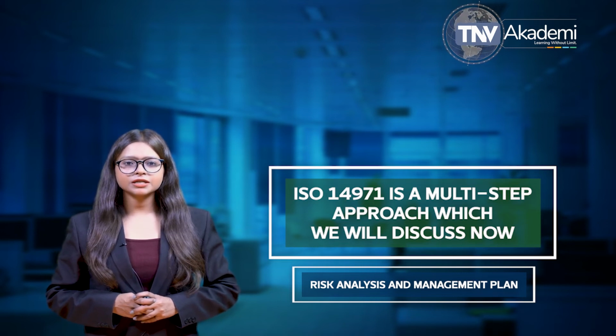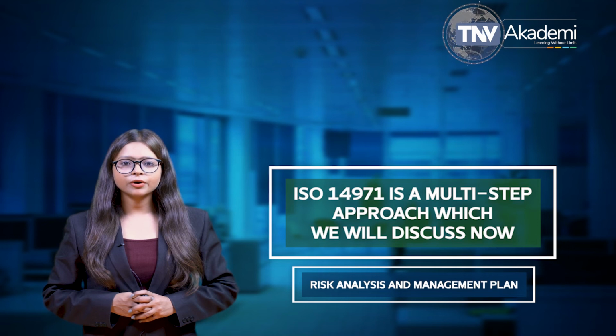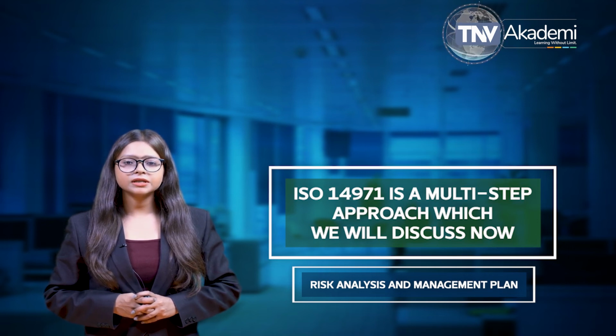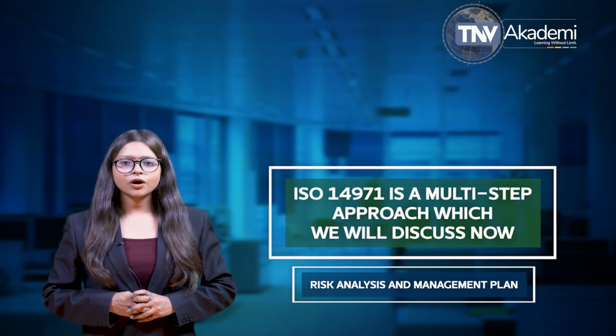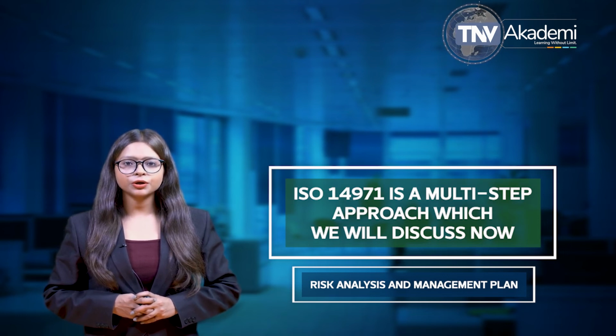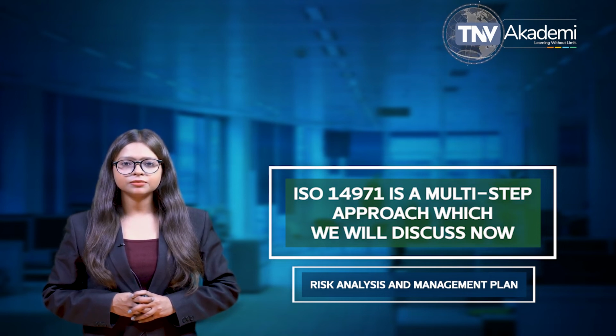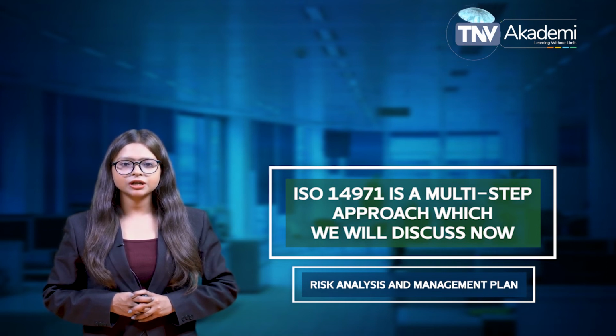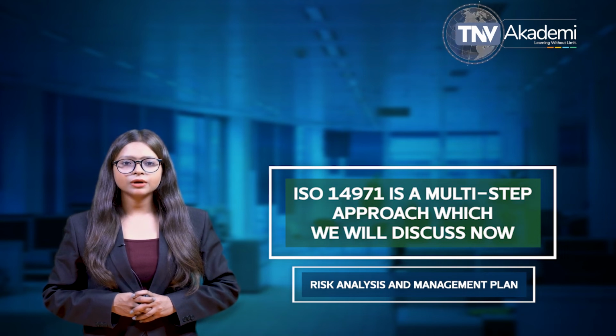The organization must define the risk management activities and which products are included within the risk management plan. Multiple products may be able to be described within a single risk management plan. The organization must describe the intended use of the products. It is paramount to describe all risk management plans throughout the product life cycle. The risk management plan must describe the roles and responsibilities of personnel. Identification of the risk management team that will be reviewing and approving documents is also necessary to address.